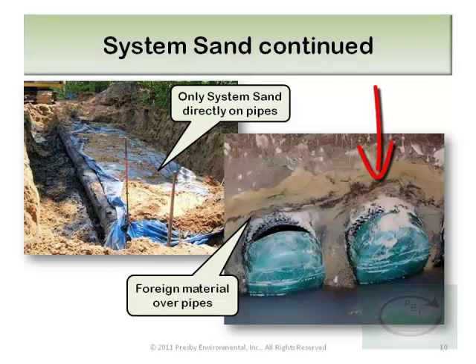It turns out the surface waters were not diverted away from the construction site, and when it rained, they ran directly into the field before it could be backfilled. The installer either didn't notice or understand how this could be a problem. Surface grading and or siltation fencing could have prevented this problem.